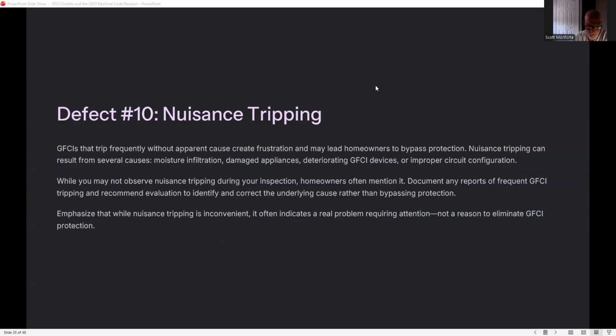emphasizing that while nuisance tripping is inconvenient, it often indicates a real problem requiring attention, not a reason to eliminate GFCI protection. So we're not going to see that during the inspection, not always. I came across it one time. I reset and it tripped, reset, re-tripped, and it was because of water in the basement.